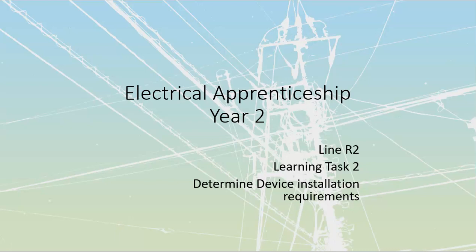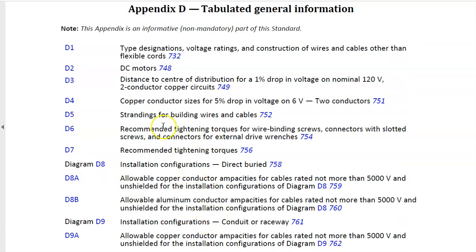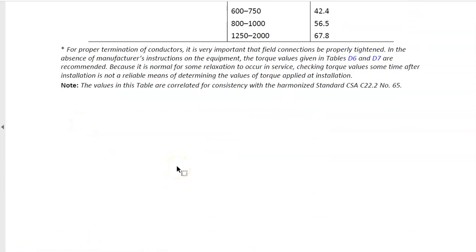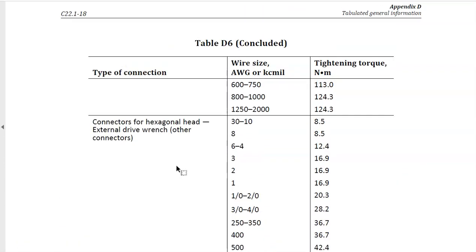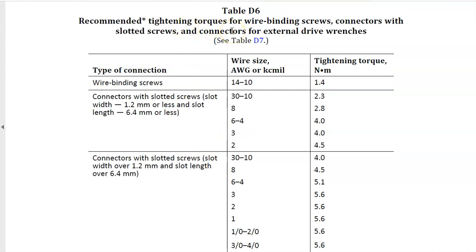Torque levels — you should be familiar with where to find your torque settings inside the Canadian Electrical Code. That's going to be all the way in the back in Appendix D, which gives us tables D6 and D7. These are recommended tightening torques based upon the size of conductors and the size of the lugs. D6 is the recommended tightening torque — note it says recommended, meaning this is what we use unless the manufacturer has specified something different. For example, for a wire binding screw with 14 through 10 gauge wire, it's going to be 1.4 newton meters.